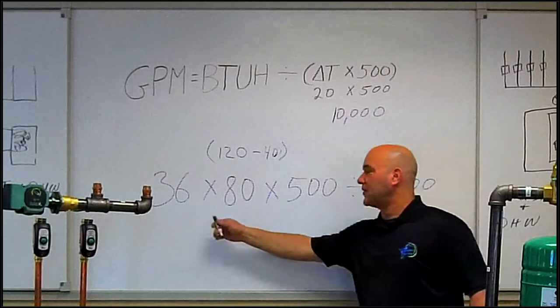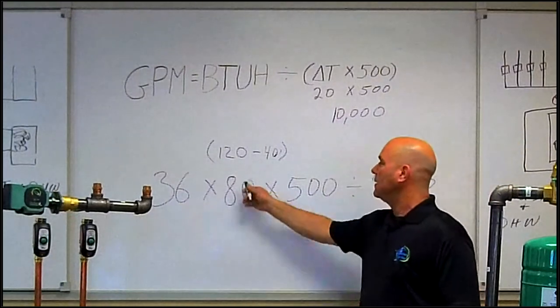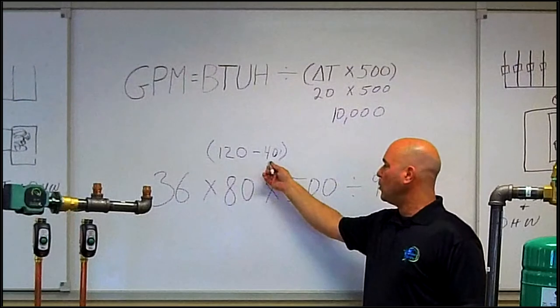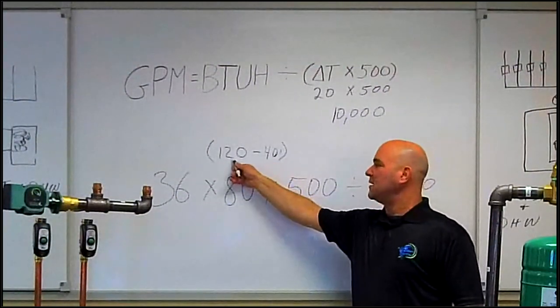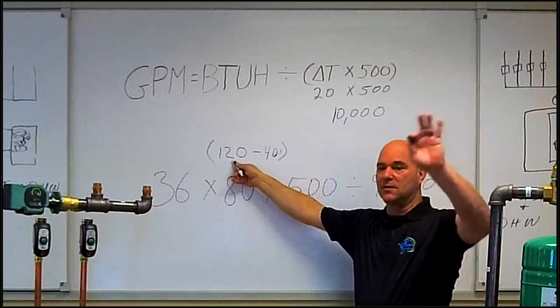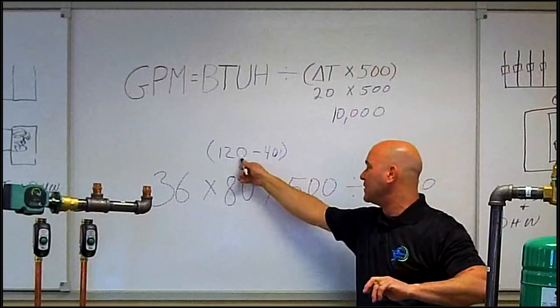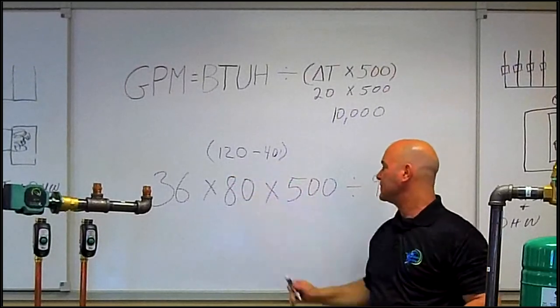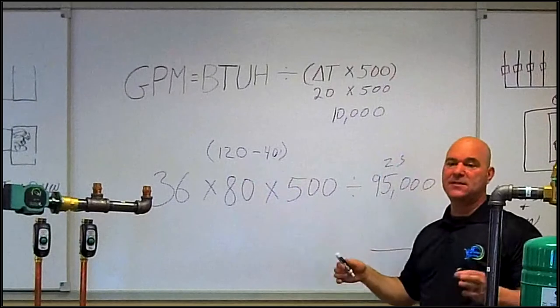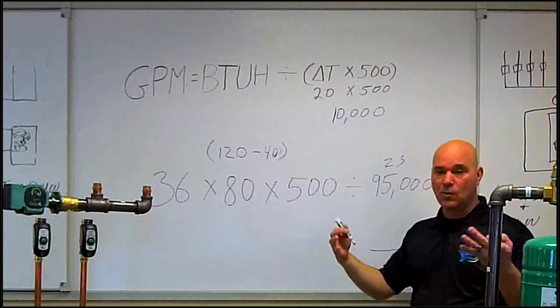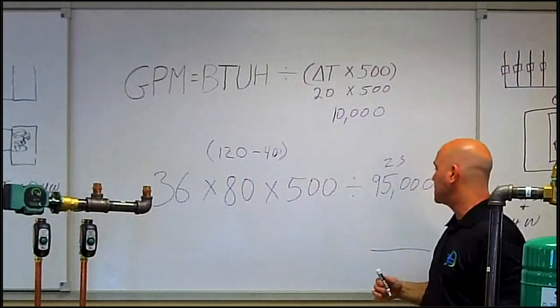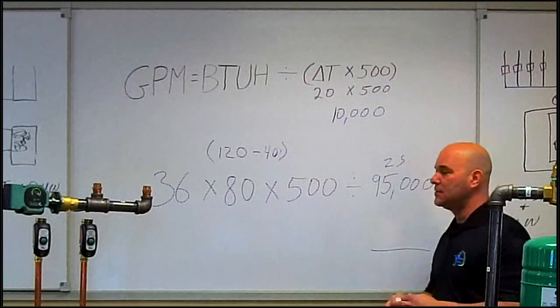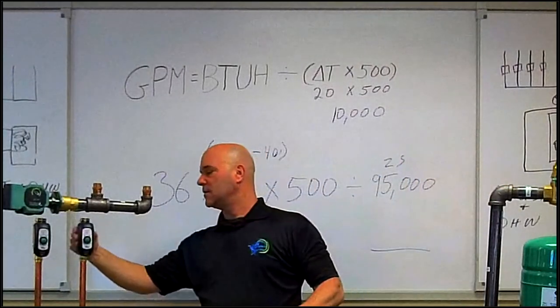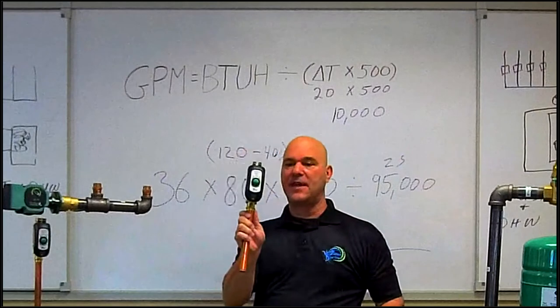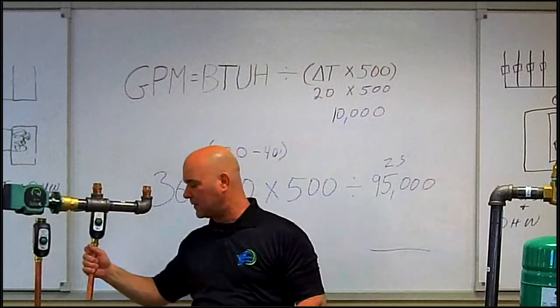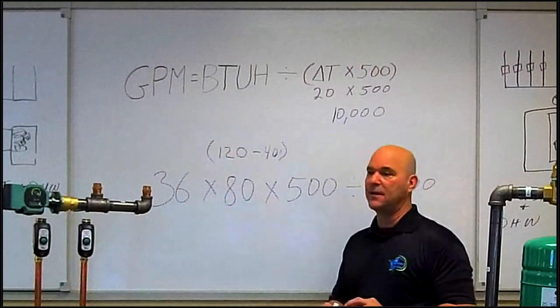So now do the math. I got a 36-gallon storage tank. My temperature differential, incoming water at 40, sending 120 degrees to my faucet, to my shower. That difference between there is 80 degrees. 500 remains the same. That's a common number we use. That's what a gallon of water can absorb and transfer energy. Here we're going to use a zone sentry zone valve. Even though I'm not a fan of zone valves on indirects, we're going to use that for this scenario.